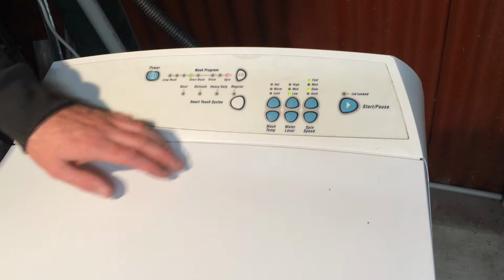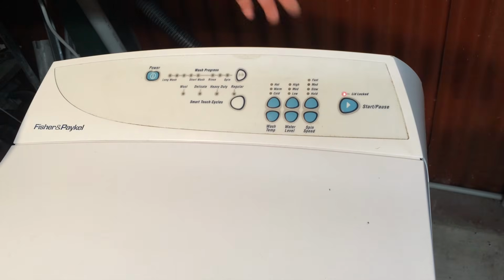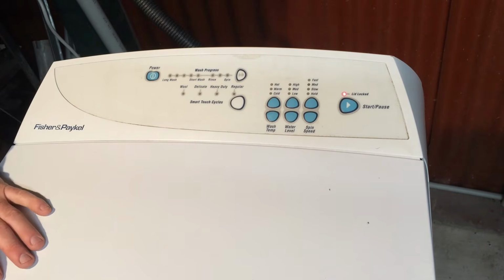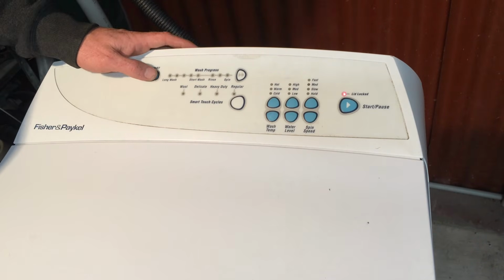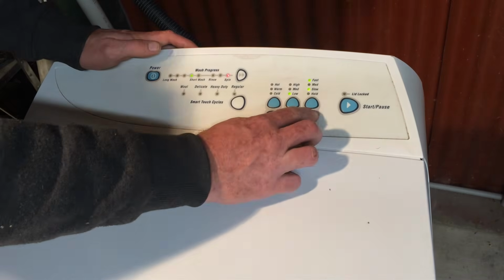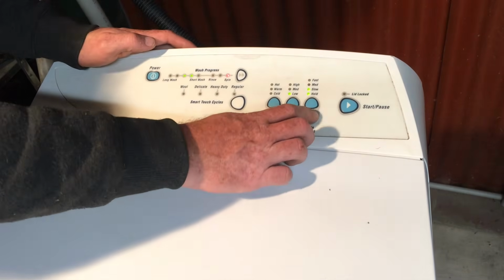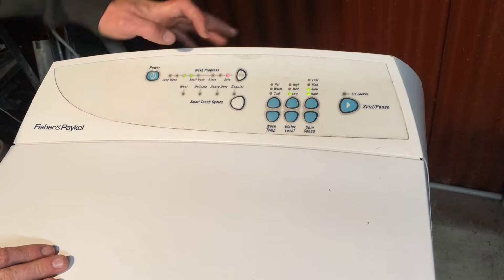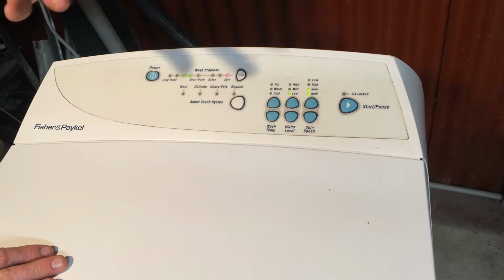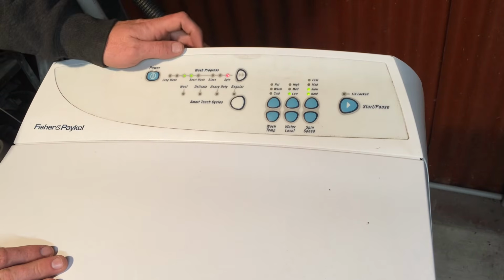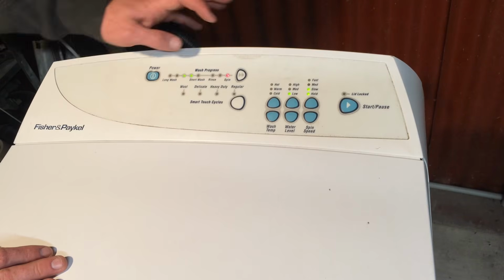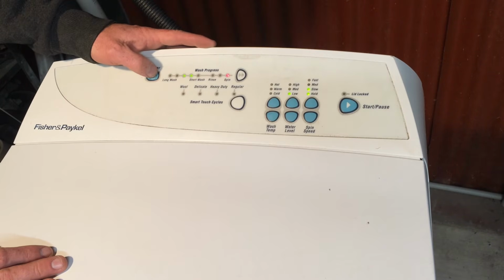Usually I just do a download, so we can actually do a download through this flickering light here into the computer, and it makes it a lot easier to get all that information out. But most of the time, the fault code is what you're going to look at. This is the last 8 cycles. We don't need to worry about the exact cycle count that happened. In the last 8 cycles, we had a fault code 49. That's probably the problem we're going to be looking at.